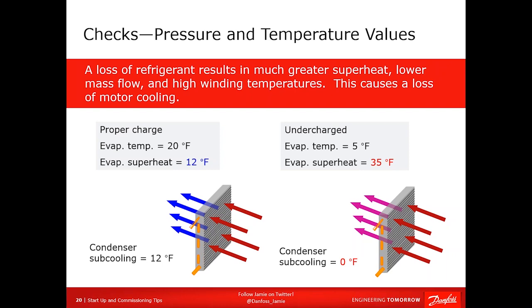If you have high superheat and a low evaporator temperature, that tells you one thing: you don't have enough refrigerant going into the evaporator. That's all that tells you, right? It could be caused by a plugged TXV. It could be caused by a plugged filter dryer in the liquid line. It still doesn't tell you you're undercharged. The last piece of information you need with a TXV is your condenser subcooling. If you have condenser subcooling, you do not need refrigerant charge, right? Unless it's like 2 degrees or something like that, and it's supposed to be 8. But if you have a nominal amount of subcooling, you do not need refrigerant charge.